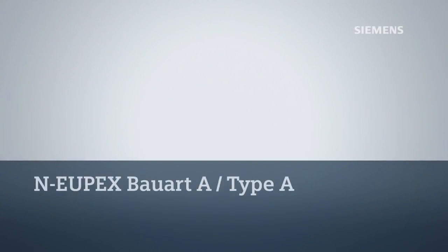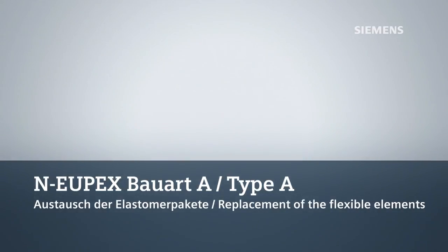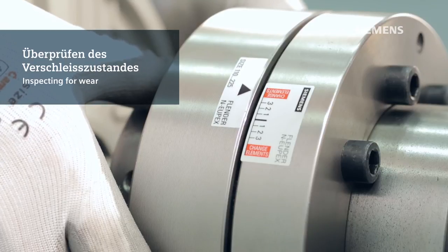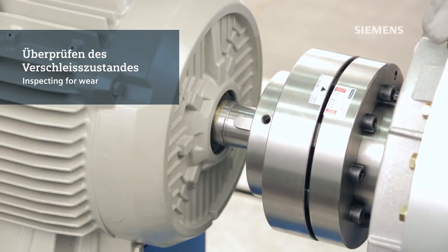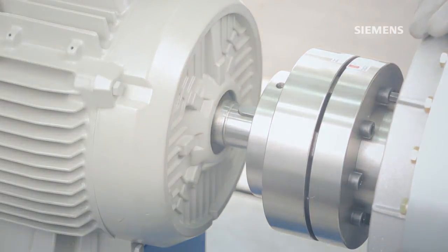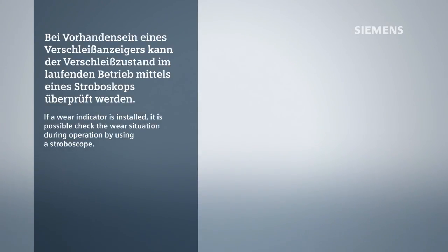This video demonstrates how to replace the flexible elements for a Siemens N-EUPEX coupling type A. The same process applies regardless of the coupling size. While manually twisting the drive shaft with respect to the driven shaft, the wear indicator will show the state of wear of the flexible elements. You will be able to gain easy access to the flexible elements by removing the bolts and pulling back part 3, the ring. The main advantage of the wear indicator is to detect the wear status of the flexible elements while the drive is still in operation.